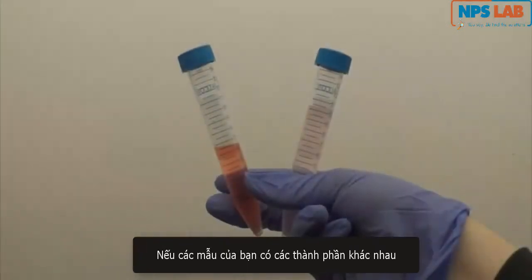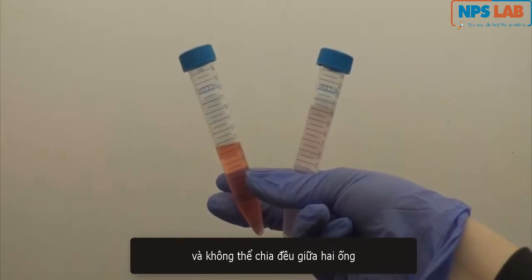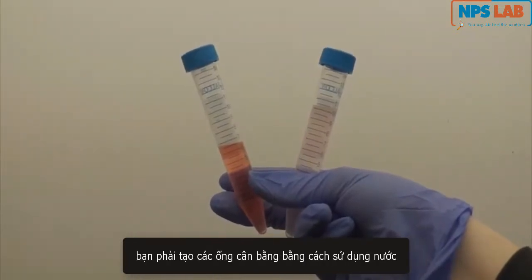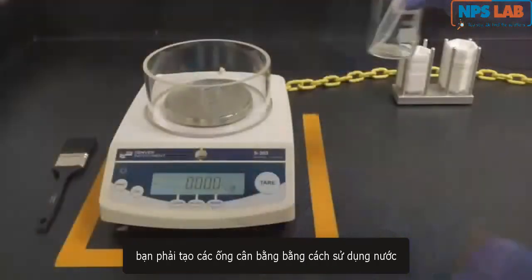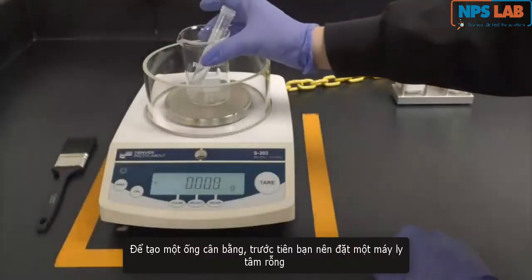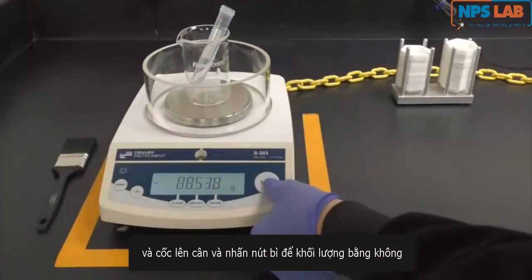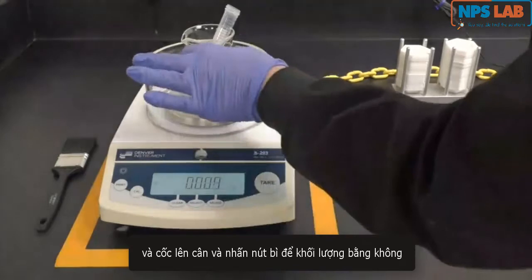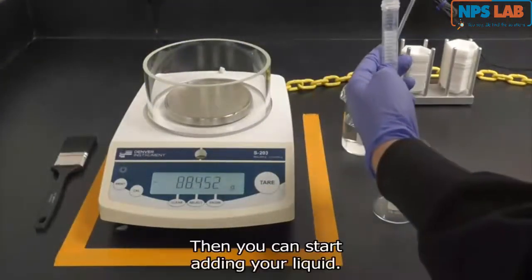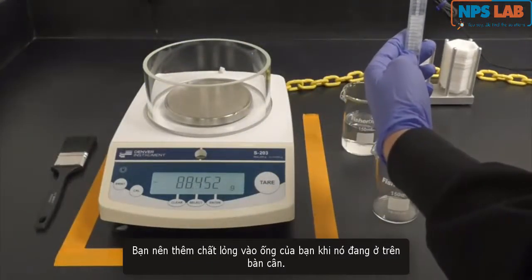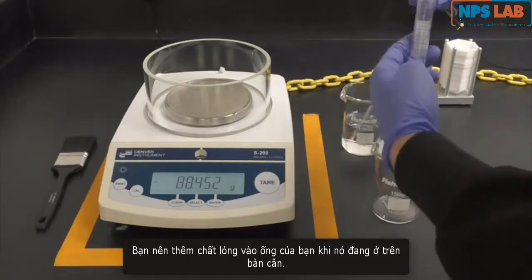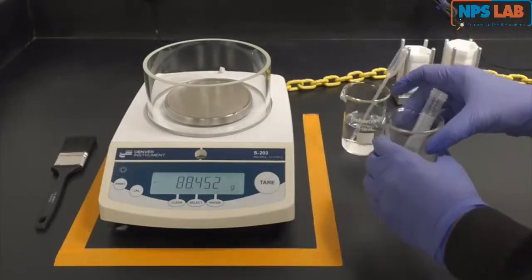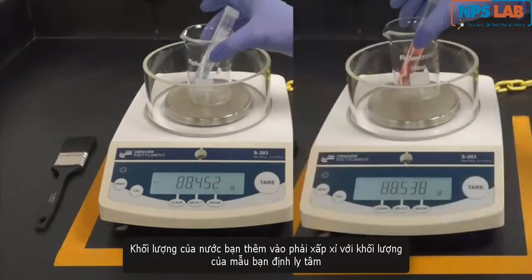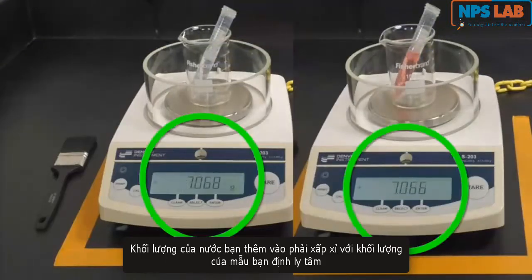If your samples have different compositions and cannot be split evenly between two tubes, you must create balance tubes using water. To make a balance tube, you should first place an empty centrifuge tube and beaker on the scale and press the tare button to zero out the mass. Then you can start adding your liquid. You should never add liquid to your tube while it is sitting on the scale. The mass of the water you add should be approximately the same as the mass of the sample you intend to centrifuge.